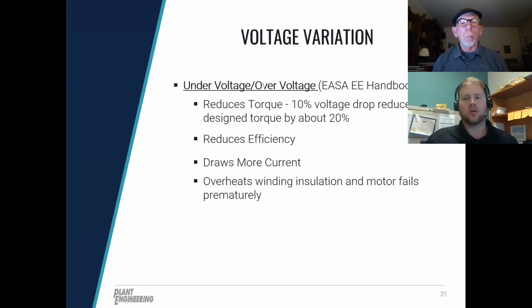So like I said earlier, we're going to get back to the discussion on voltage. Motor terminal voltage is a good place to start for the power quality conversation. You want to always verify rated voltage on the motor nameplate. So sometimes you may have multiple voltages on the motor terminals. I've also seen motors that may be wired for one voltage, but supplied with another voltage. That's not good. I've seen incorrect wiring many times. Terminal 3 is hooked up in place where terminal 8 should be, and vice versa. That's not good. One tool I like to use is put out by the Electrical Apparatus Service Association, EASA, their electrical engineering handbook.